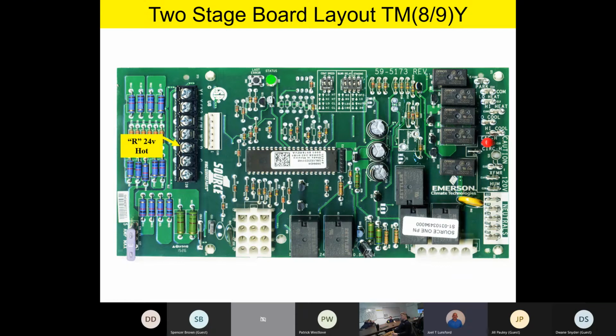R is our 24 volt hot. That's very, very common in the industry. G is our fan call from the thermostat. So if we want to have fan operation, we can energize the fan call on the thermostat sub-base assembly. So G is our fan call. And then finally, C is 24 volt common. Any questions or comments on the basic low voltage wiring so far? Everybody good?